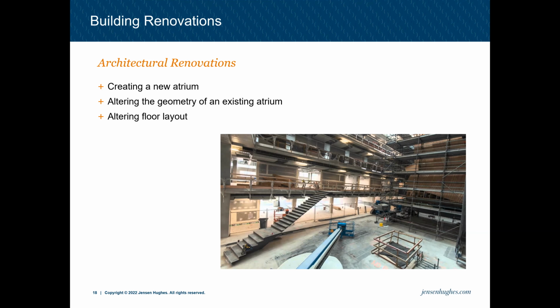But if we're altering the geometry of an existing system or an existing atrium, then CFD analysis and FDS analysis are required to see if that system is still maintaining its original design intent. Because if we're reducing the size of our atrium in half, our fans might not be able to keep up with the same fire load or size to maintain that tenable environment on a higher level. Altering the floor layout, including adding corridors that connect to the atrium, could cause a couple of issues too, because smoke can travel down these areas. It's just something that we want to keep in mind and identify early, so that we can coordinate this early and don't run into issues down the road of the models not working or not maintaining tenability, so we can mitigate those issues but still keep the same types of floor plans.